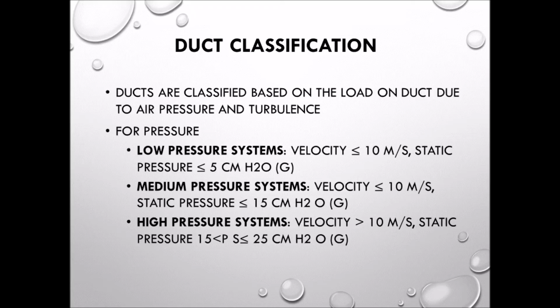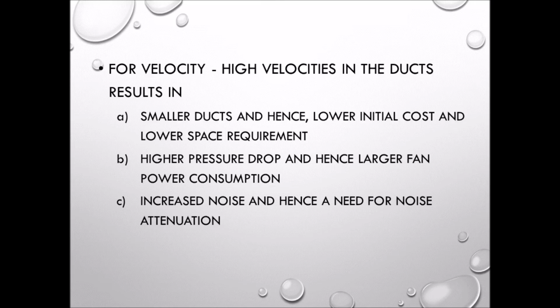So this is the characteristic for pressure and for velocity. High velocities in the duct result in smaller ducts and hence lower initial cost and lower space requirement. Higher pressure drop and hence larger fan power consumption. Increased noise and hence a need for noise attenuation.